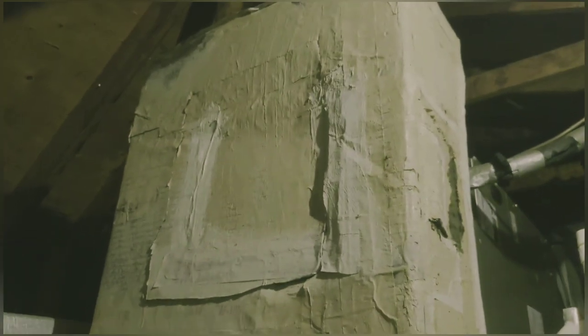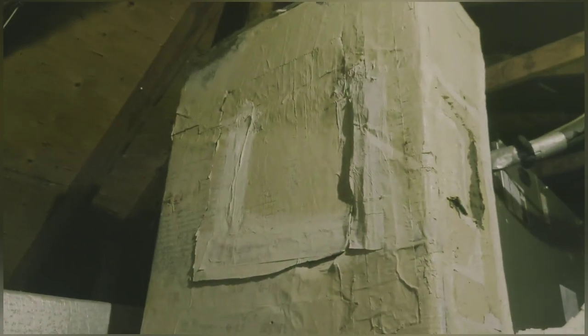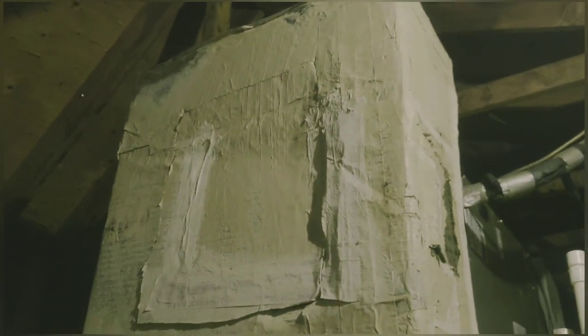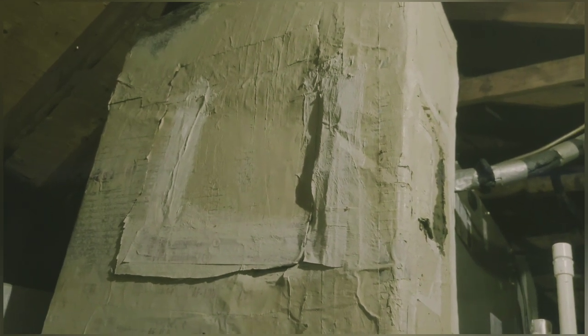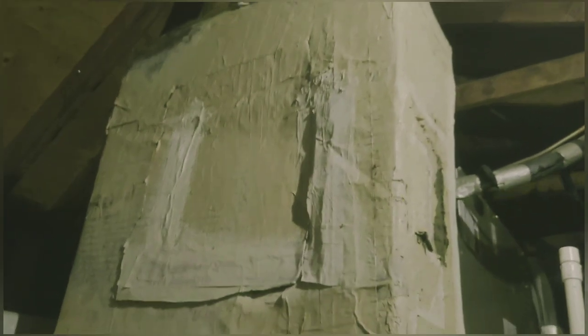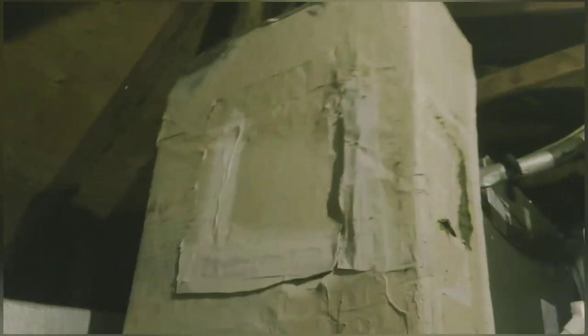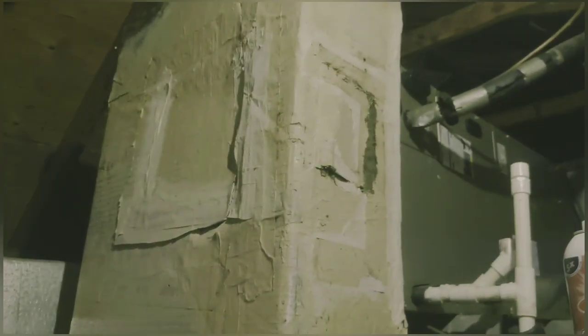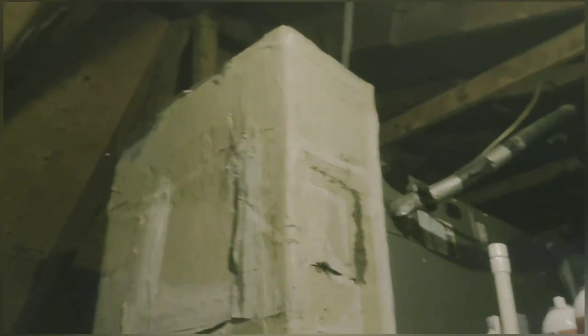Okay, and then finally, you just want to make sure you put your cover back on. It's a beveled piece — you put it on there in the same rotation and orientation that it came off. Use a good duct tape, depending on what your material surface is like. You can even get some mastic tape, or you can get aluminum foil-backed silver tape, but silver tape won't stick very well to the mastic surface. And that's it — pretty easy. Just be careful and pay attention. Thanks for watching.